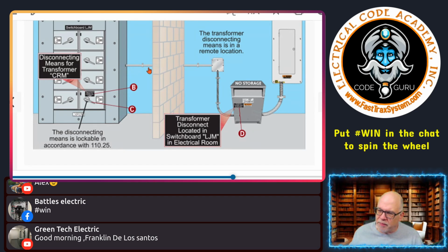And so here, maybe the engineer didn't know, or wherever they designed it, there just wasn't enough room. Now, this looks like there's probably enough room to put one. But anyway, the choice was to not put the disconnecting means here. So if that's the case, this is your primary, and here's the label that's required. It says transformer disconnecting located in switchboard LJM. You can see this says LJM here. You probably can't see that, but it's right there. And it says in the electrical room.